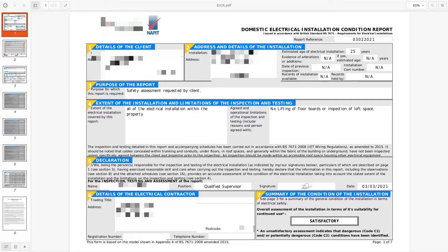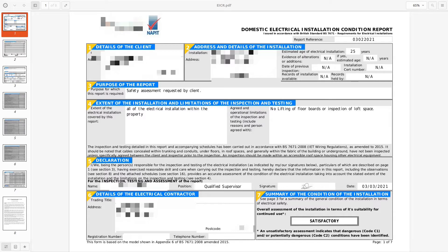At this point here I stopped. Let's have a quick look at this company who's carried out the work and find out that they're not actually registered to carry out electrical installation condition reports using the NAPIT branding. So then I looked at the certificate under a little bit more scrutiny and there appears to be several mistakes that cast doubt on the validity of the certificate.